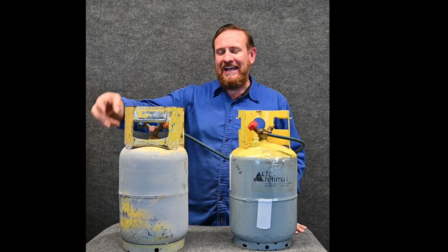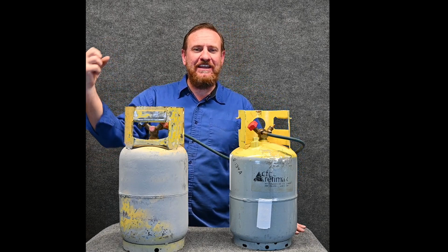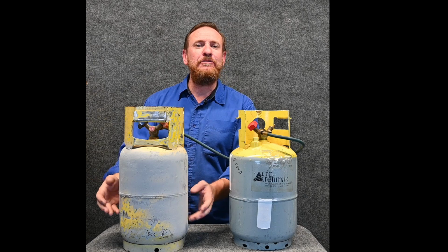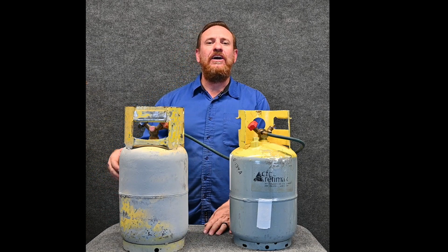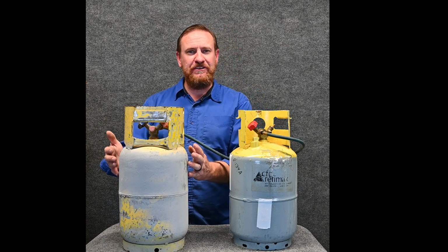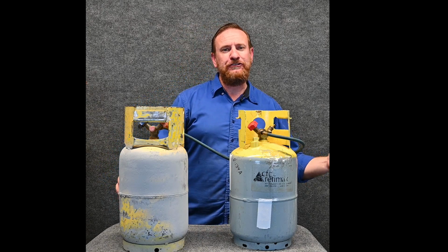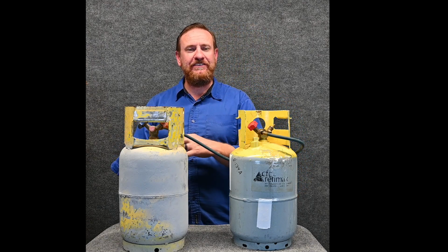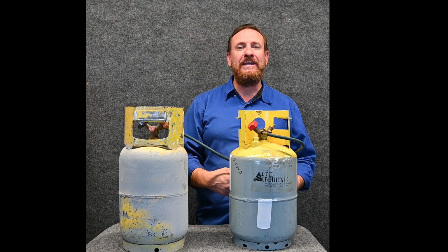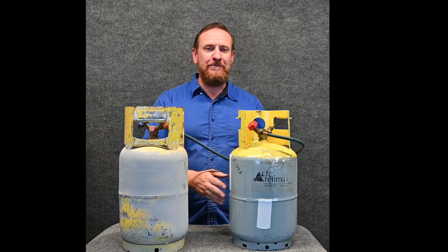What was happening was, as I was pulling refrigerant out of this tank, the refrigerant that remained boiled into a vapor. As it boiled into a vapor, it caused it to absorb heat. So the temperature of this tank started to drop. So refrigerant started migrating this way. Well, as it was migrating over to this tank, we had the same thing. Refrigerant was boiling from a liquid into a vapor, so the temperature of this tank was dropping.